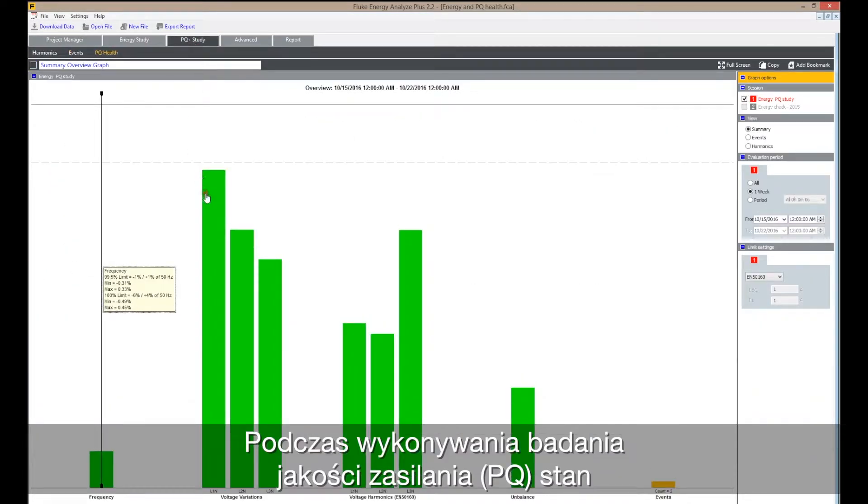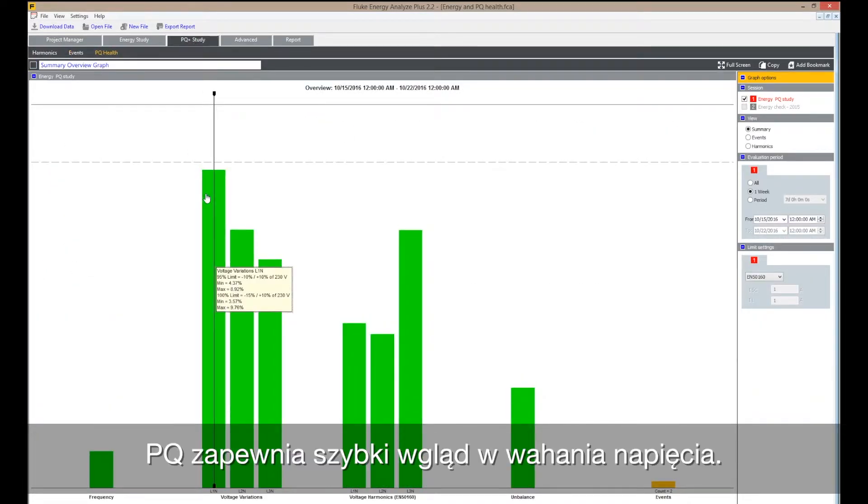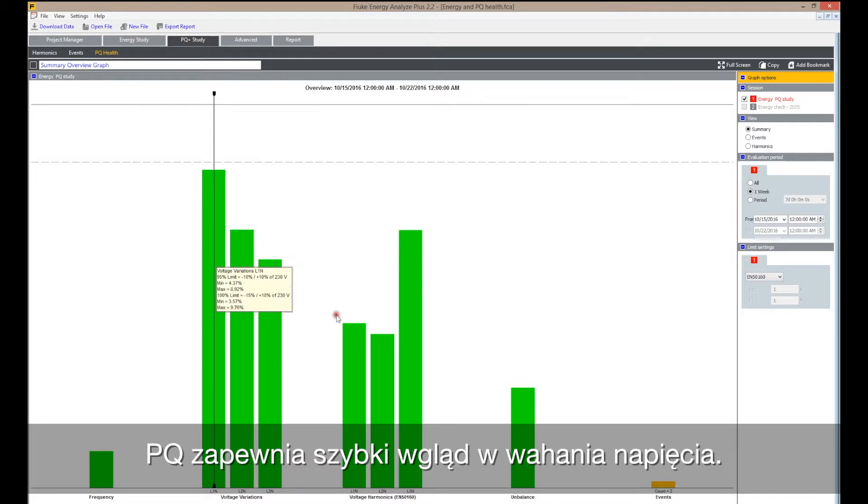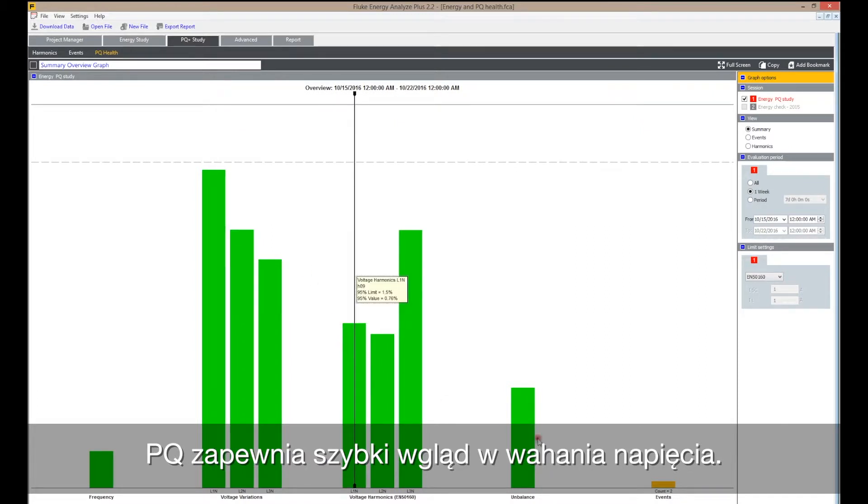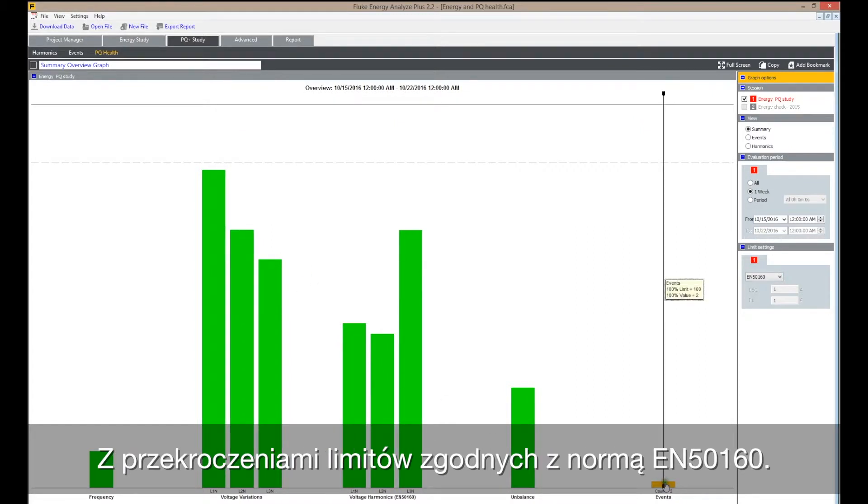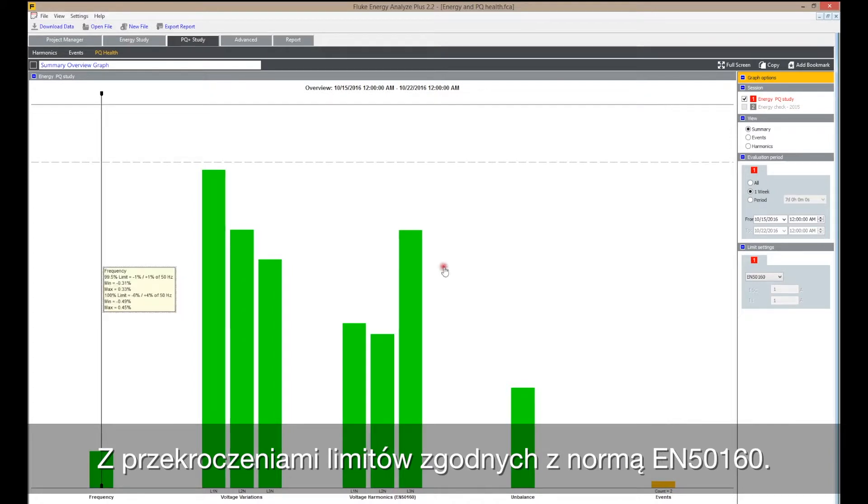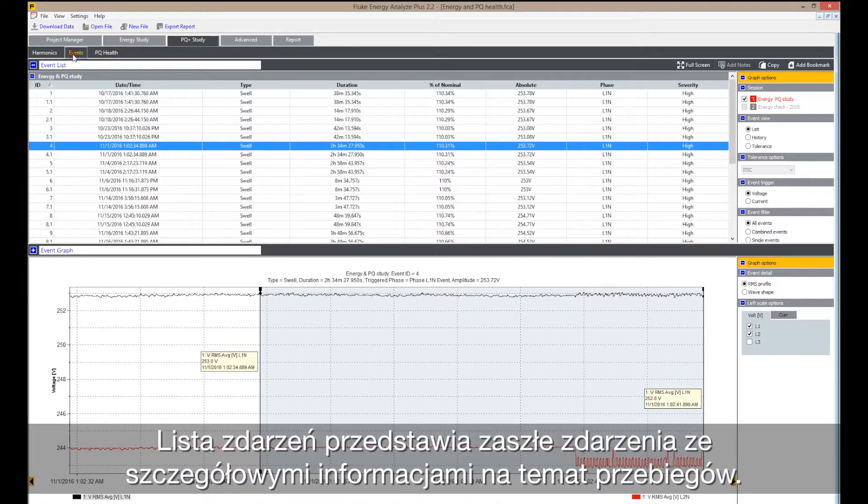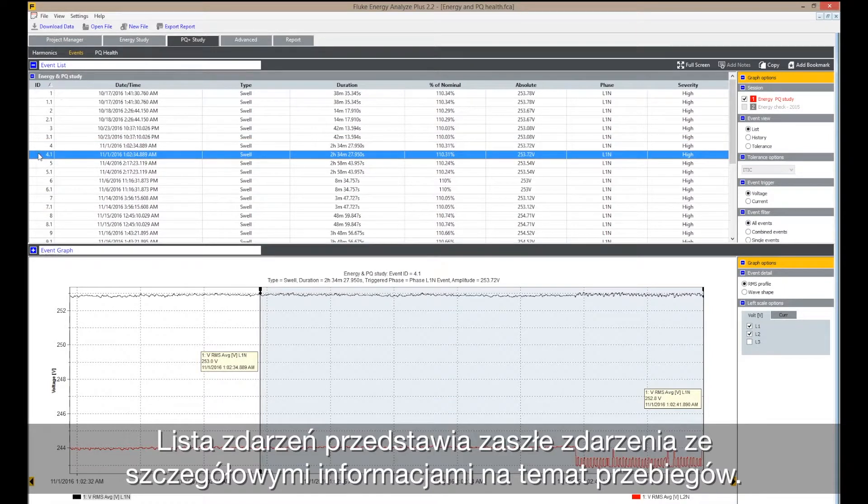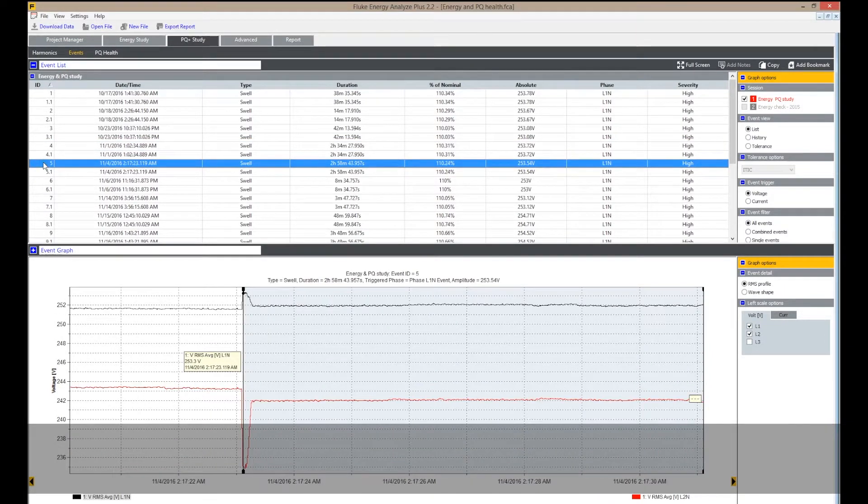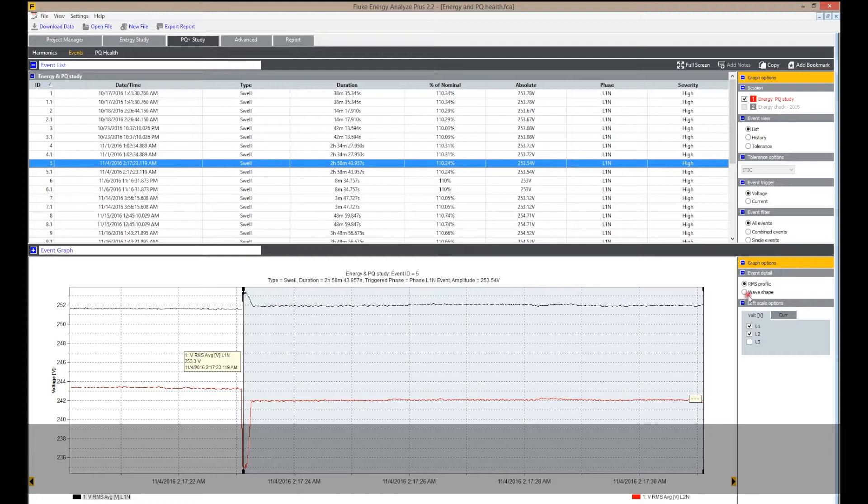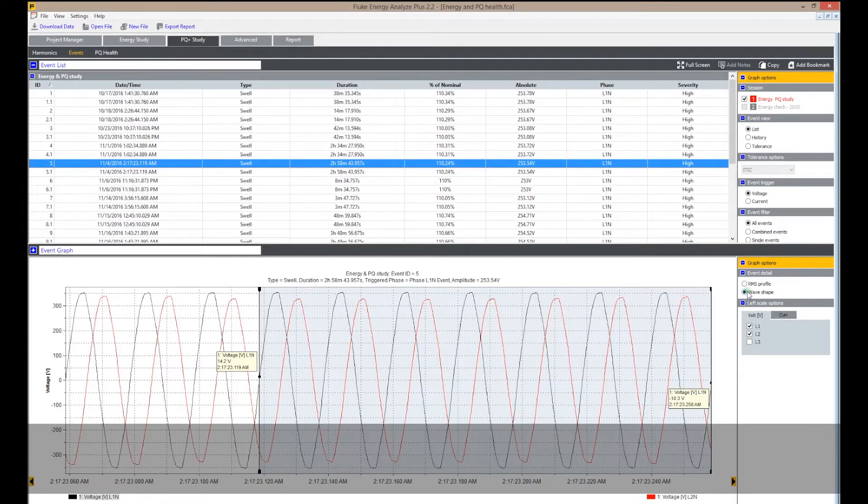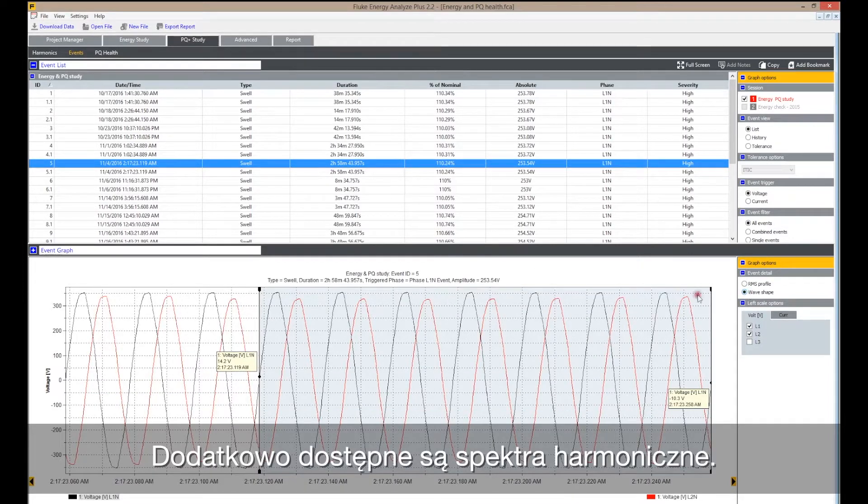If you want to perform a power quality study, then PQ Health gives a quick overview about voltage variations with exceedances of limits according to EN 50160. The events list shows the events that took place along with wave shape details. In addition, harmonic spectra are available.